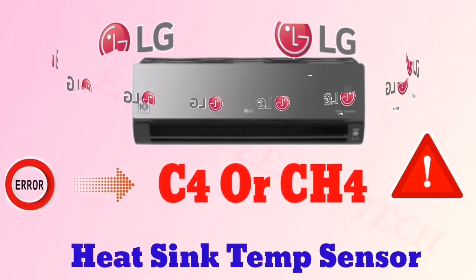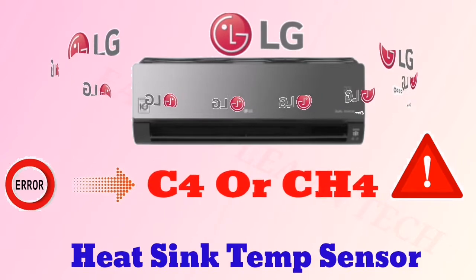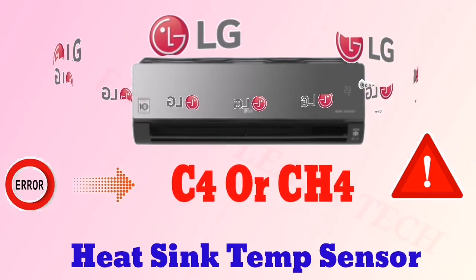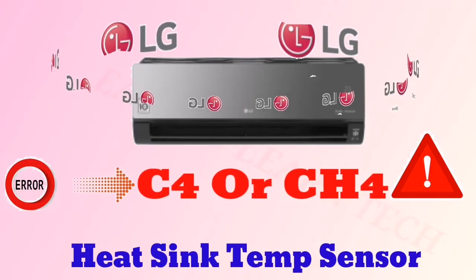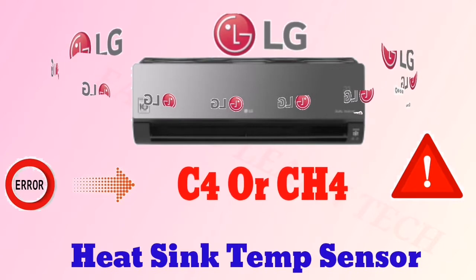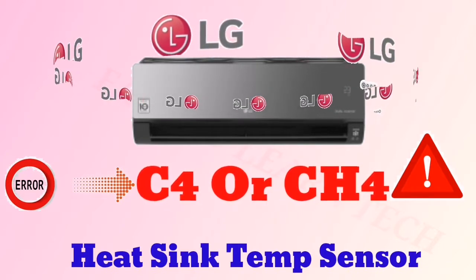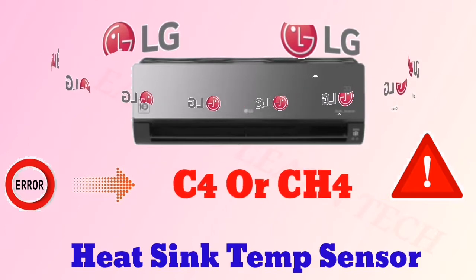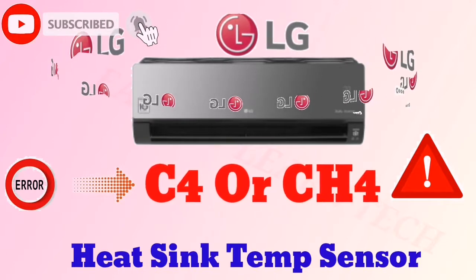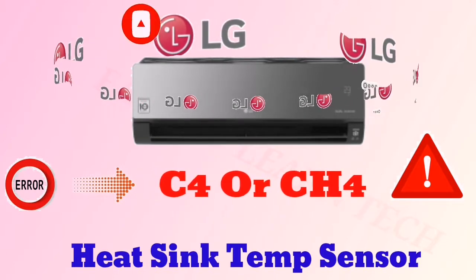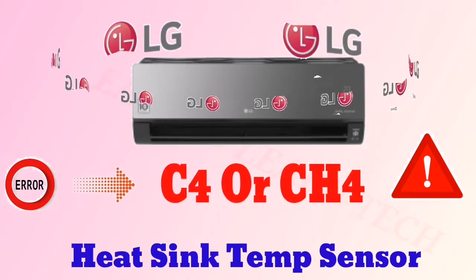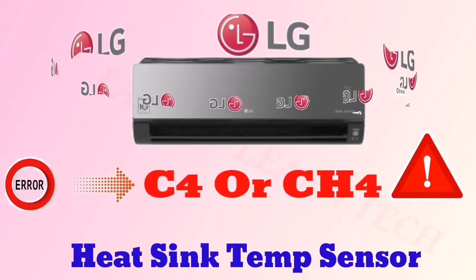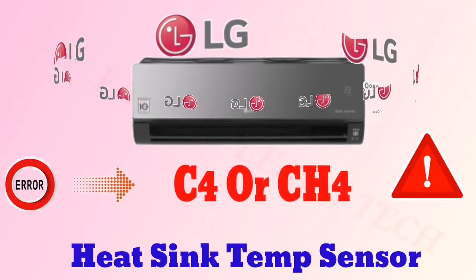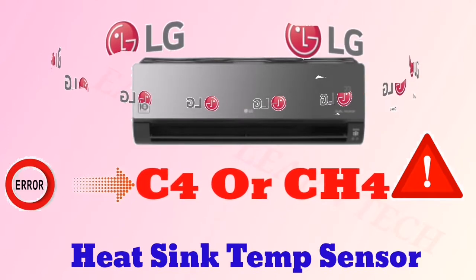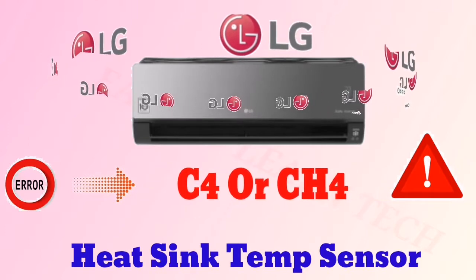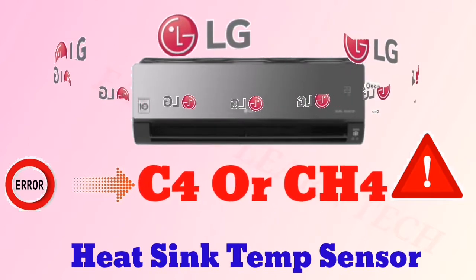Let's see the next error code and its solution. Next error code, if you get C4 or CH4 on your outdoor unit, it means the heat sink temperature sensor. The heat sink we find just below the PCB. The work of the heat sink is to absorb the heat produced by the PCB. In that we have one sensor. If the sensor is faulty, at that time it will show this error. First of all, you have to check the resistance of your sensor. If the resistance is perfect, it means your sensor is good. If the resistance is not perfect, it means your heat sink temperature sensor is faulty. And if you are getting the resistance properly and again you are getting the same problem, then you have to check the output of your PCB, whether it is perfectly connected or loosely connected, or well placed or not. And again, if you are getting the same error, then you have to check the PCB, and if the output for our sensor is not coming, then you have to change the PCB, and your unit will be in working condition.